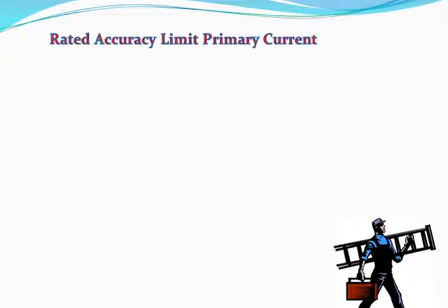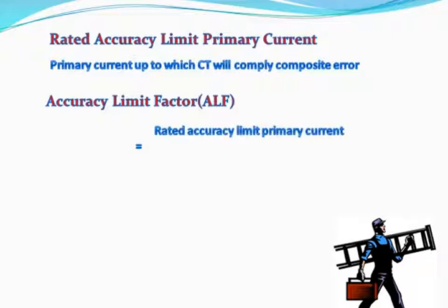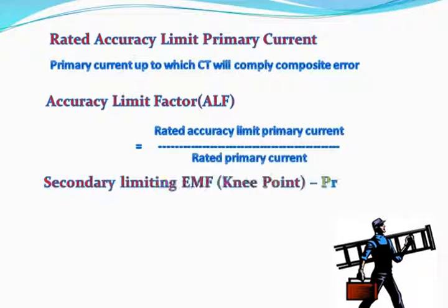Rated accuracy limit primary current: the primary current up to which CT will comply with composite error. Accuracy limit factor, or ALF, is equal to rated accuracy limit primary current divided by rated primary current. The secondary limiting EMF, or knee point voltage, is calculated accordingly for Class X CT.